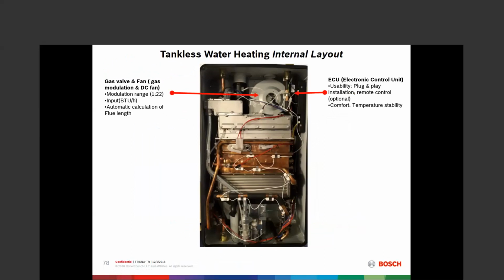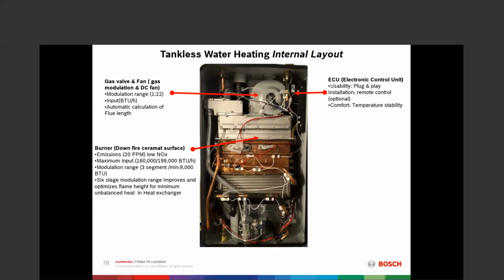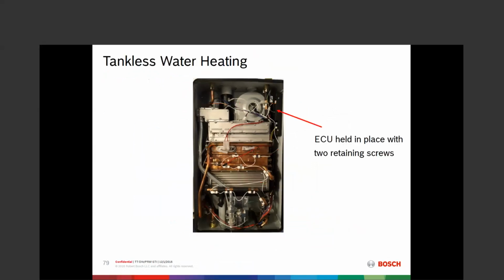We've got our fan, the ECU, that's where all the logic is. Down-fired, copper heat exchanger, stainless steel condensing heat exchanger. The ECU itself is held in place with just 2 screws. We lose a board, we know we're going to have to replace it. So if the house takes a lightning strike or a surge or something like that, and we lose a board, we want to be able to replace that as quickly as possible. In doing that, it is actually a universal board across the entire range of heaters, all 7 heaters. It's the same control replacement for all 7 units.